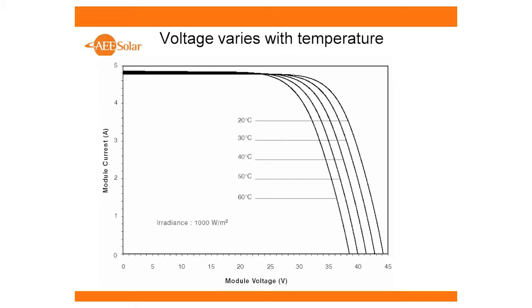and how it reacts to sunlight. All right, and so then we go into voltage, and we see that the IV curve slides left to right with temperature. So as the temperature goes up, the curve slides to the left, or to lower voltage, and as it gets colder, it slides to the right. Okay, and this is just the physics of the photovoltaic effect and what's going on in the band gap in the PV cell, and all that good stuff, which results in what we see in the field: lower voltage on hotter days and higher voltage on colder days.